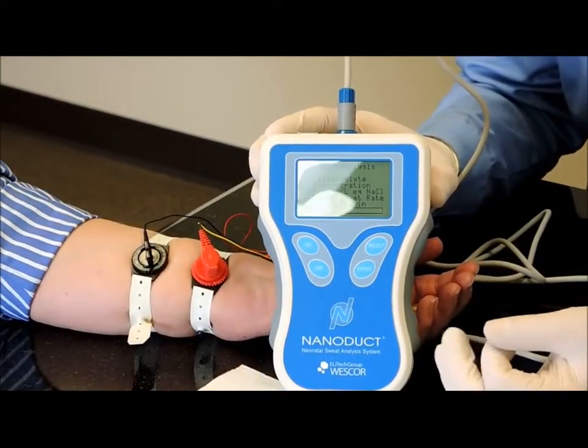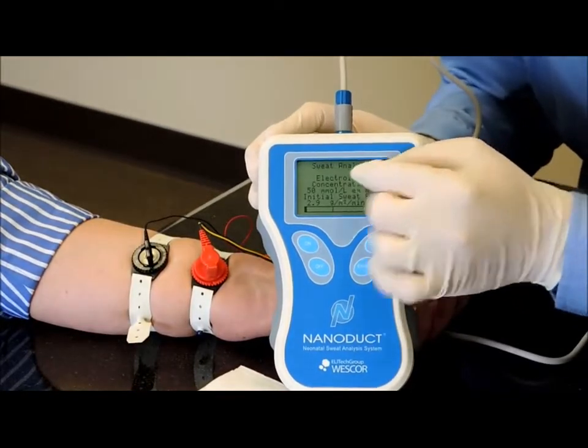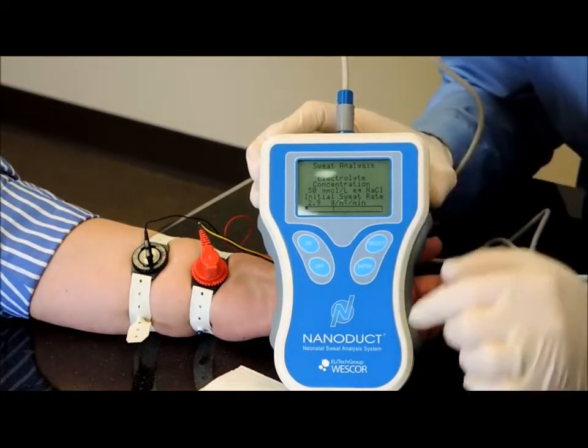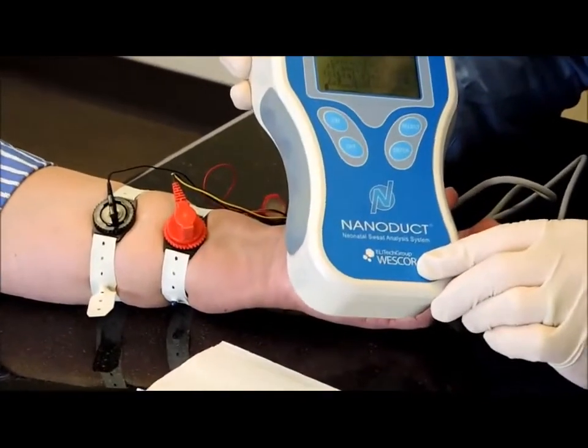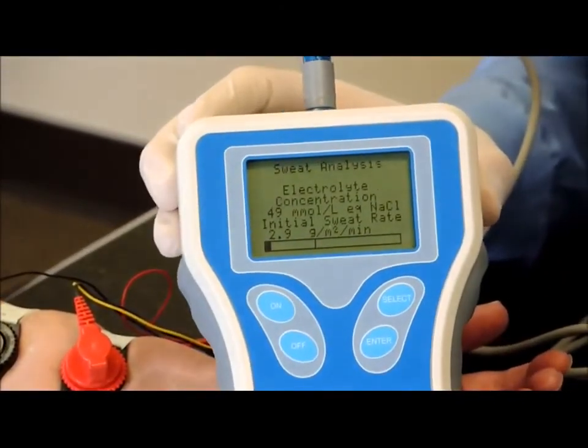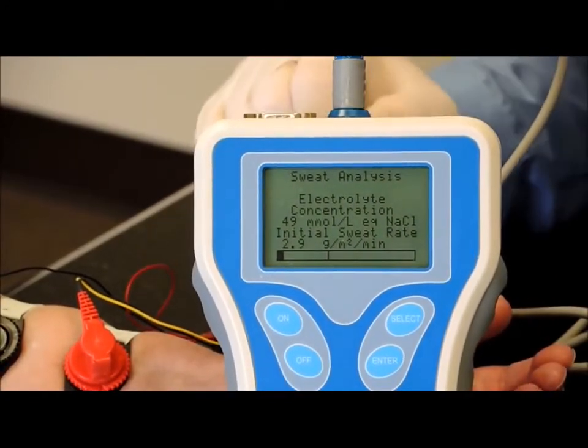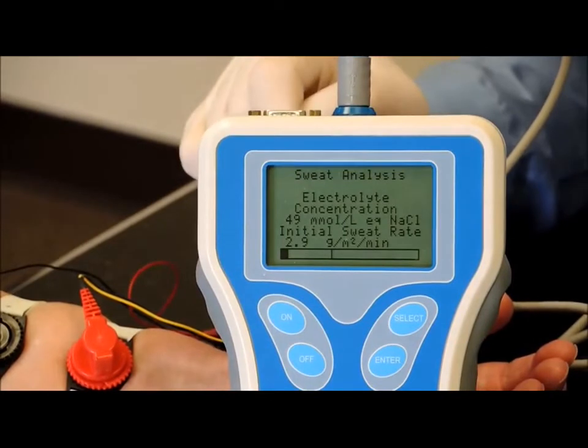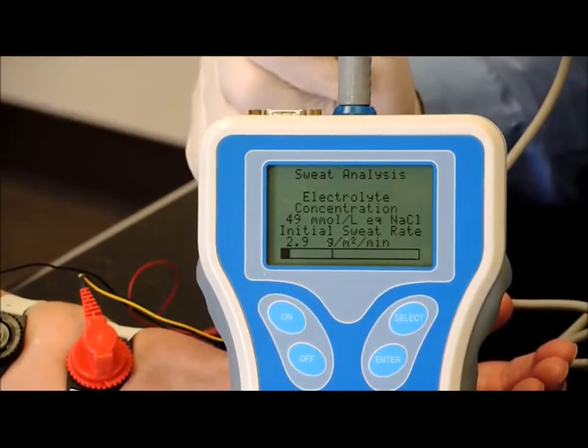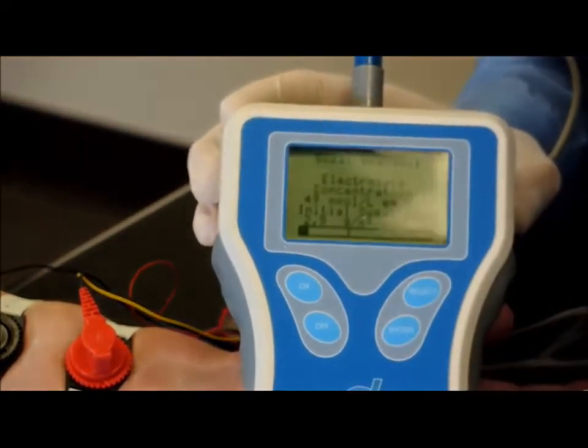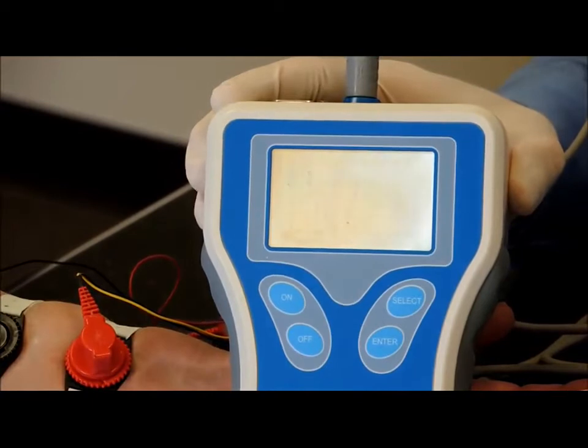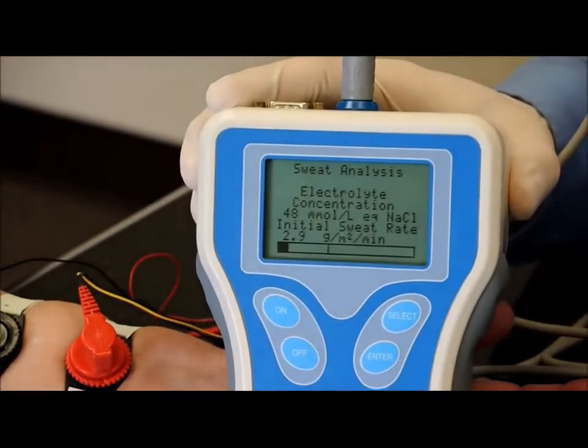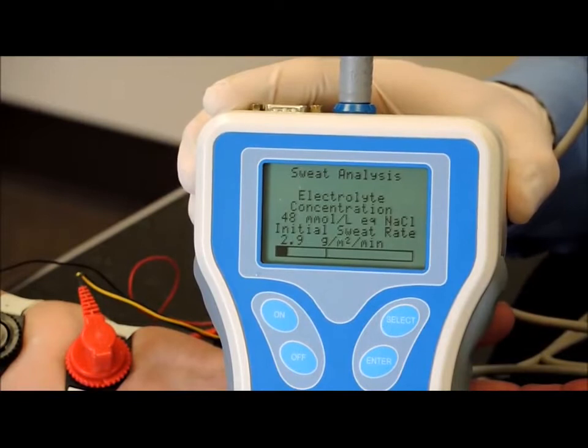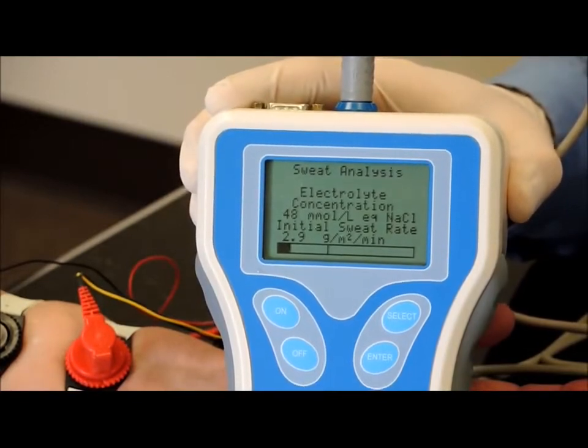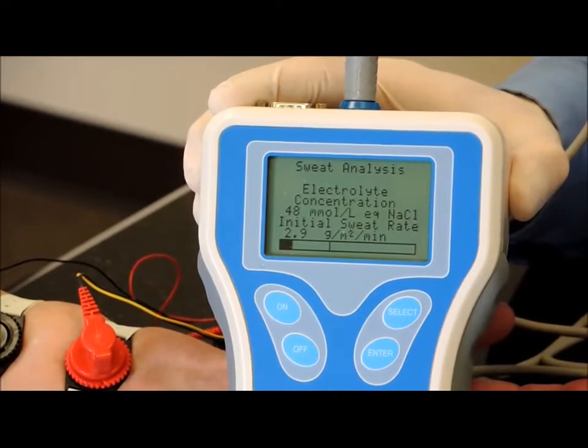Now the sweat has reached the second electrode, and you'll see that the readings start appearing on the screen. So the first reading is 49 millimoles. That is the conductivity value of the sweat coming from the patient. You also see below she has a sweating rate of 2.9, so that's her sweating rate. It needs to be above 1 in order to be valid according to the CLSI sweat testing guidelines. So we're well above that 1, which is good.